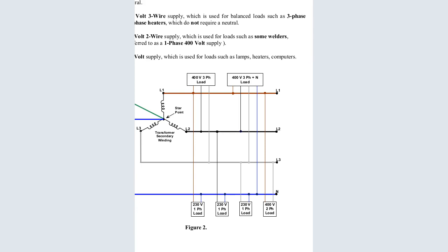This one is getting the load from this. This one is getting the load. These are now single tapping, balancing the loads. And this one is getting its loading from here, from line 3. Load 1 will get its live from line 1. Load 2 will get its live phase from line 2. And load 3, the same, will get from line 3.